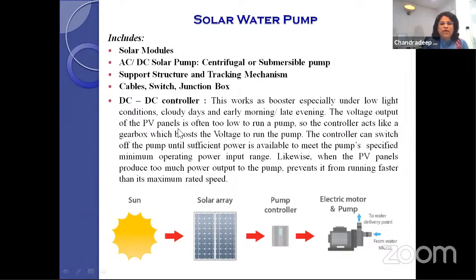The voltage output of the PV panels is often too low to run a pump, so the controller acts like a gearbox which boosts the voltage to run the pump. For example, consider a DC pump of 24 volt, because I'm using a DC pump. If input is less than 20 volt, the pump will not run, or suddenly it may increase to 22 volt. So whatever the fluctuations in the input voltage, the output is boosted to 24 volt and continues. The controller can switch off the pump until sufficient power is available to meet the pump's specified minimum operating power input range.